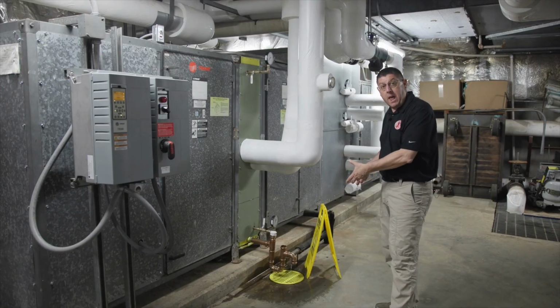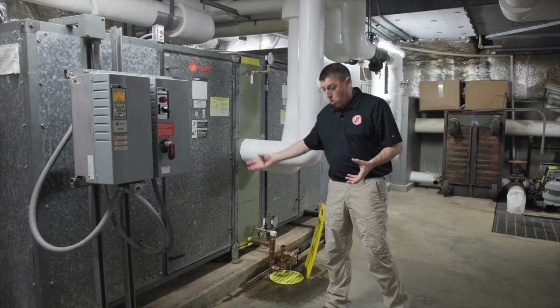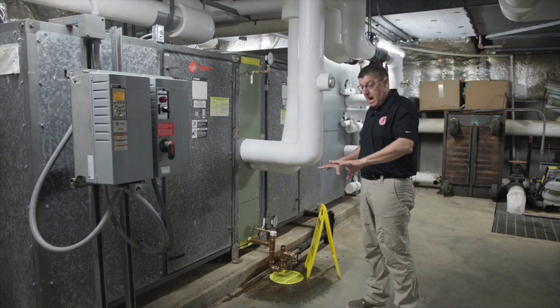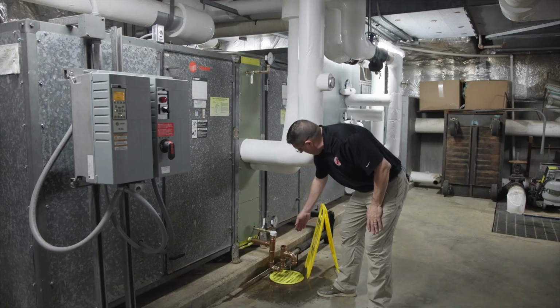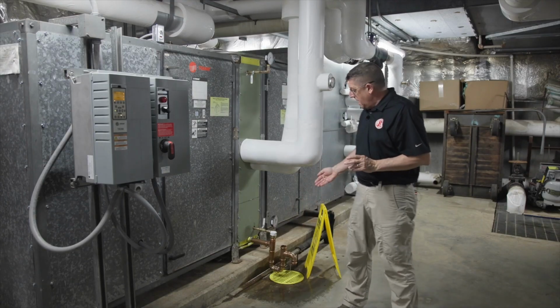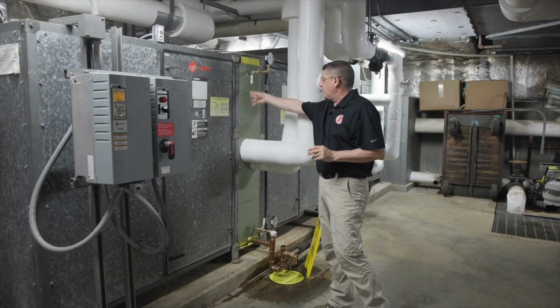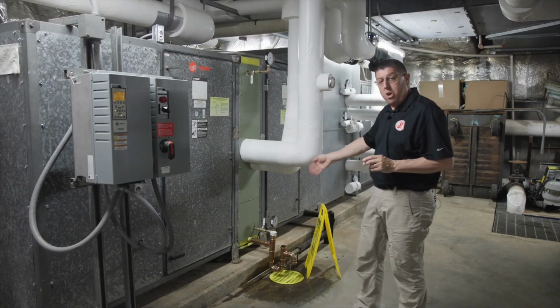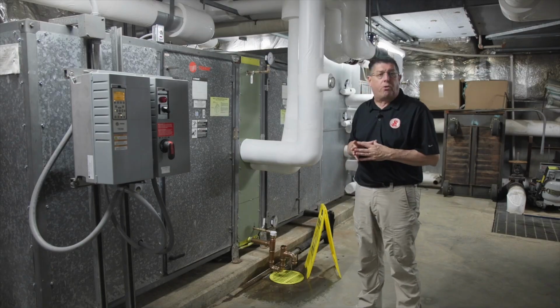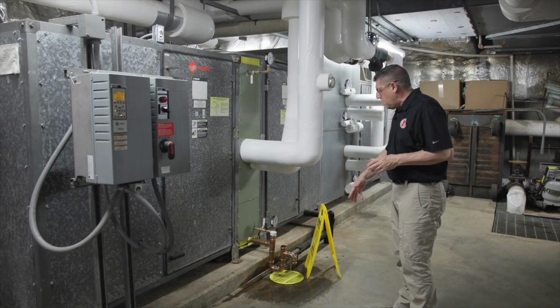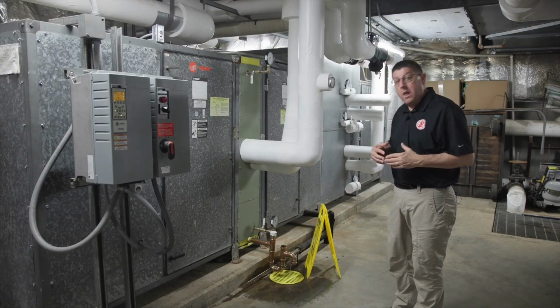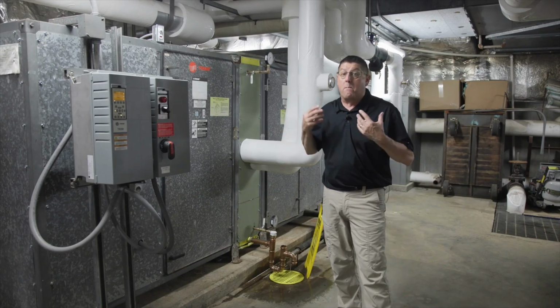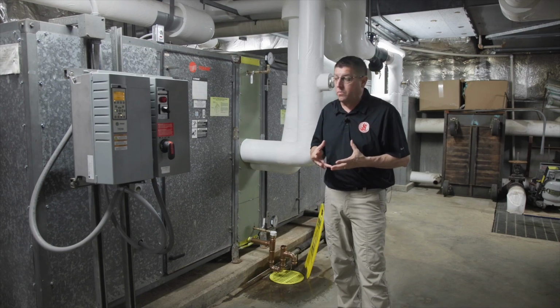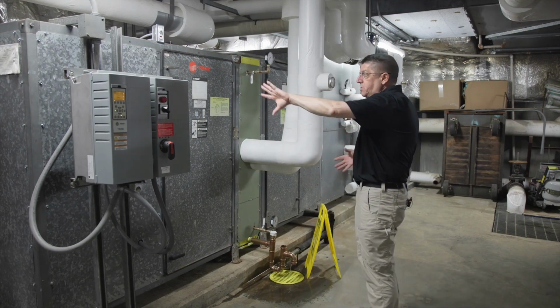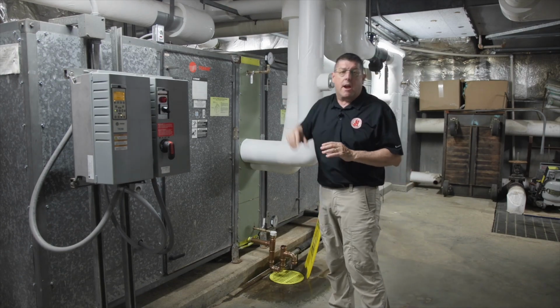Without a trap, as this thing is bringing in air, it's going to suck air from this room, which could be the floor drain or anything else. So this trap that we've assembled here is perfect. It's allowing any condensation that's dripping down this coil to be accumulated and fall directly into this floor drain. Yeah, there's a little bit of splash going on. It's hot outside. We're producing a lot of condensation. And then the air is passed through here and it goes up through the entire system.